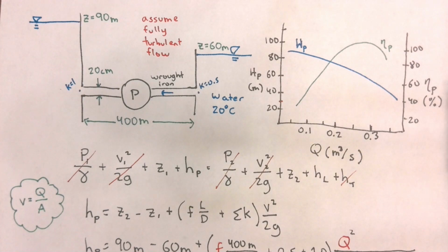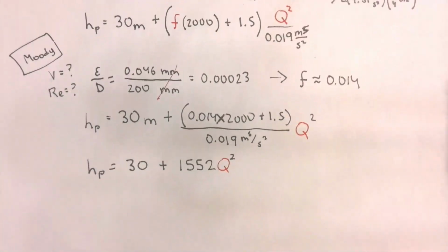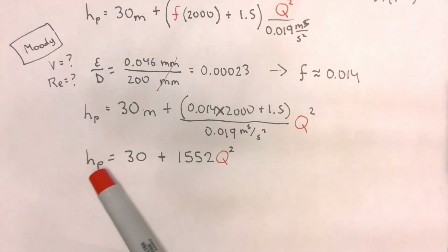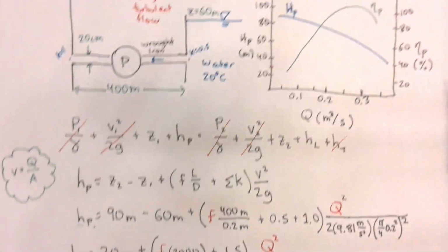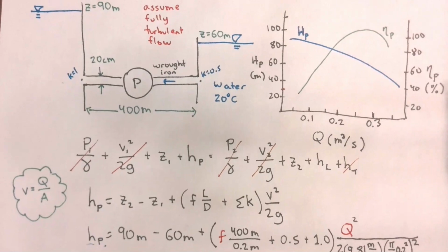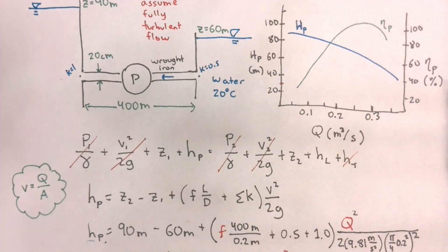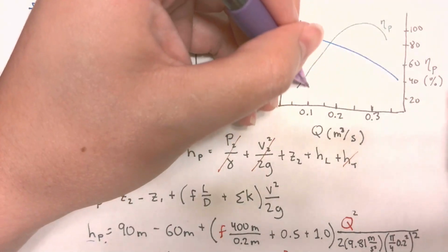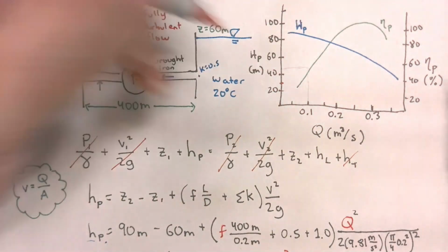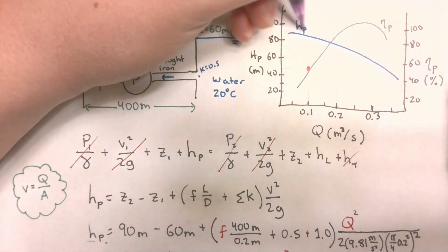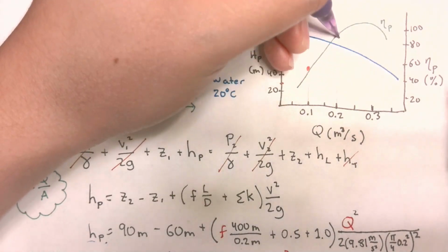Cool. All right, so somebody give me the value for the system demand when the flow rate is equal to 0.1. 45.52? Yes, sir. Perfect. So that means that when the flow rate is equal to 0.1, my pump head required will be 45.52. So it's somewhere around here. What about 0.2? 92.08. So somewhere around here, right? Let's pretend that my lines are straight.